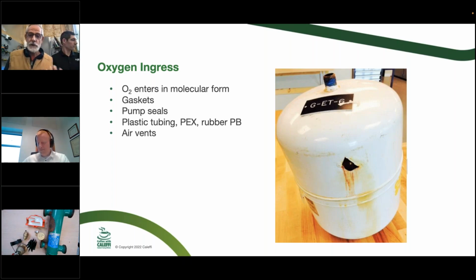A good air separator, of course, will keep it down to a minimum, but this is what happens when you have a system where oxygen is getting in on a pretty regular basis. You've got a high temperature system, you've got non-barrier tubing, and oxygen's getting in there, and it's going to go after any ferrous component. The weakest is usually the expansion tank because the metal's the thinnest there, and that's what happens when you see a job where there's a bunch of old expansion tanks laying on the floor when you arrive. Pretty much tells you you've got an oxygen ingress, and it can happen through that air vent. Like I said, it can happen around tubing and stuff like that.